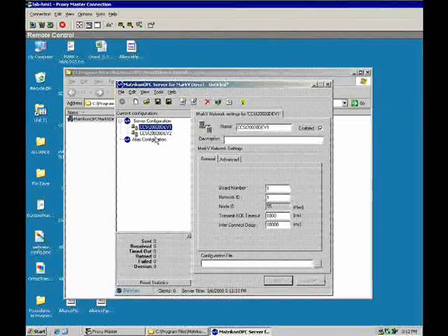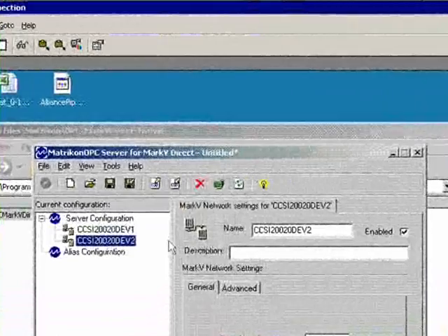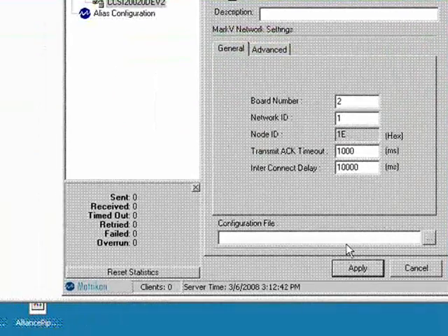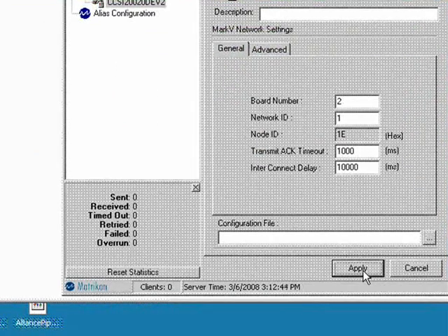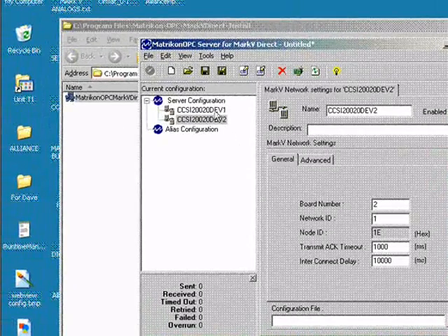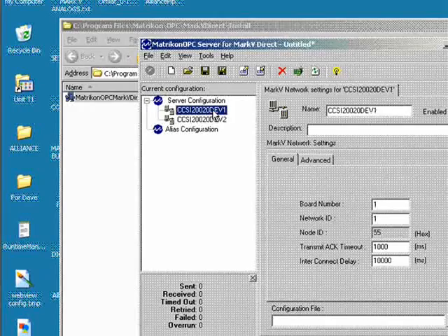You'll notice now that you might have two links in the server configuration. One of these will be used by the TCI to talk to the ARCnet card. The other will be used by our OPC server to talk to the ARCnet card. In this case, it is best to disable the device link to the ARCnet card which will be used by the TCI, so we don't have interference.